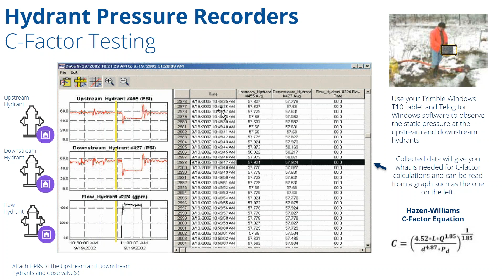One of the last applications for our hydrant pressure recorders is really a combination of everything we've talked about, whether it's C-Factor testing, fire flow testing, or capacity testing. All of that together provides the core building blocks needed to calibrate a hydraulic model, or to provide your engineering consulting firm with accurate data to help calibrate the model. Once the data is in our software, we're able to do things like steady state analysis, extended period flow analysis, fire flow tests, and C-Factor tests. All of this gathered information is the core data engineers need to help calibrate their models.